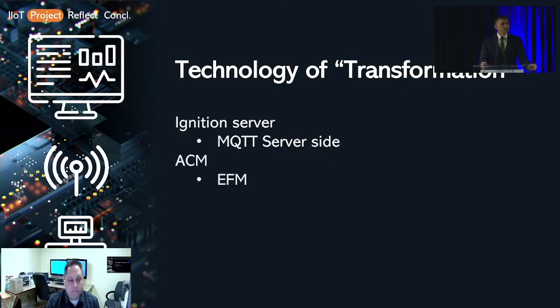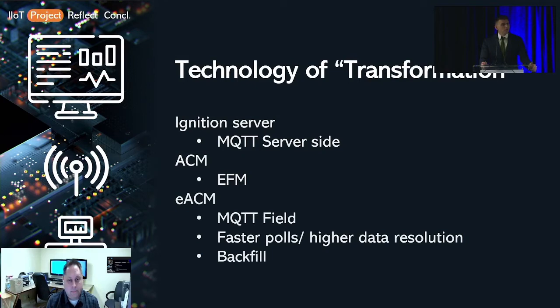This wasn't revolutionary, but it was new for them. Basically, this is how they wanted to get their EFM data back from the field. And where a lot of the work went into was deploying eACM, or Edge ACM. This was deployed in the field to bring that MQTT from the field back up to the server, to decrease bandwidth through MQTT usage and report by exception, and then get them higher resolution data for the tags they wanted, as well as do backfill when comms went out, feeding it back up to the Ignition system and all the other MQTT clients.